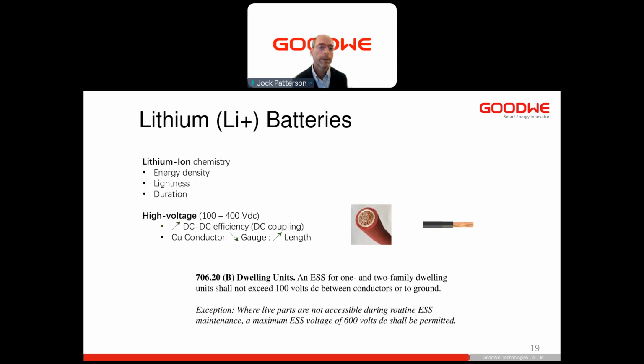This presentation is about single family or duplex homes, not multi-family residential systems, but the code will tell you that you shouldn't be using these high voltage batteries for these single family homes. Well, they make an exception. If you are using an ESS that's in a cabinet, it's protected, there are no conductors or contact points that result in high voltage exposure, then you can use ESSs up to 600 volts.